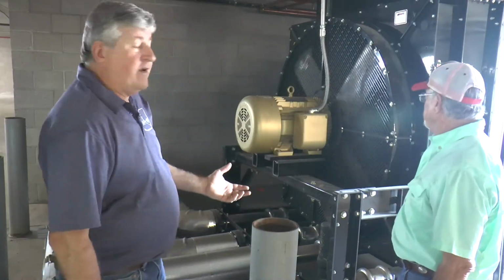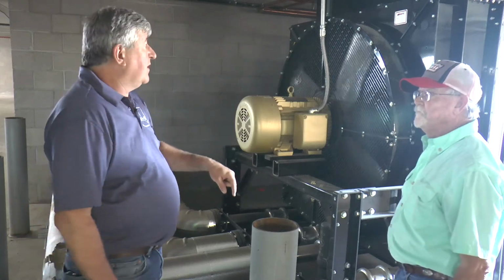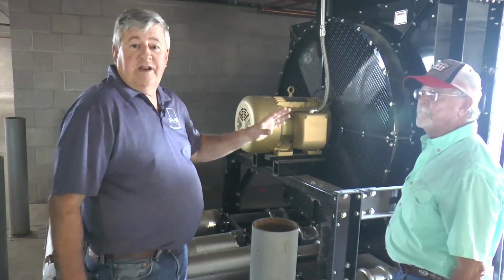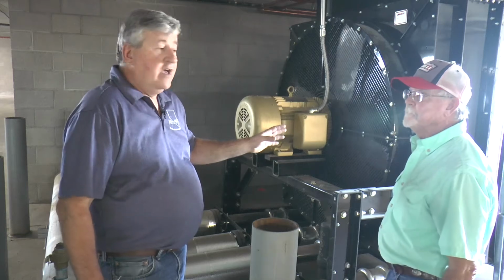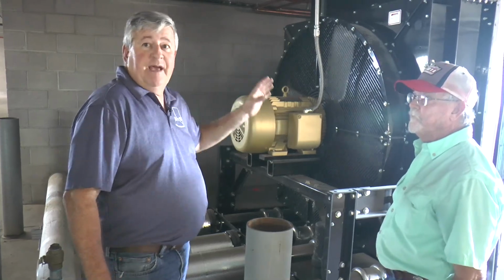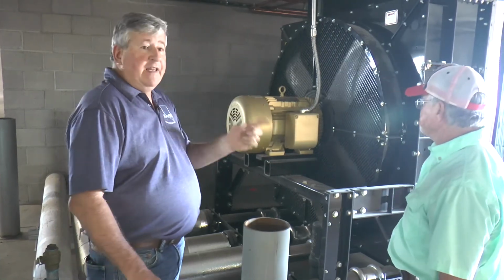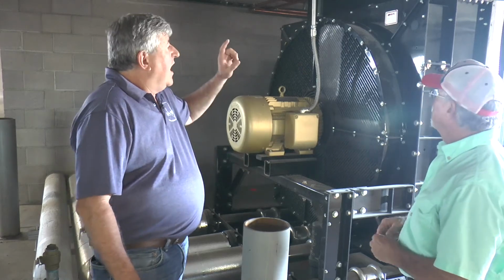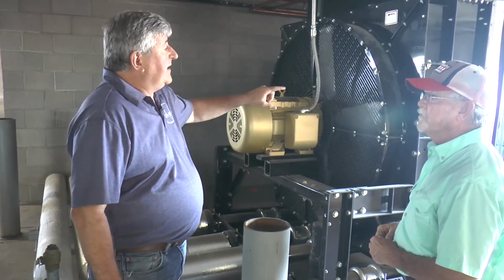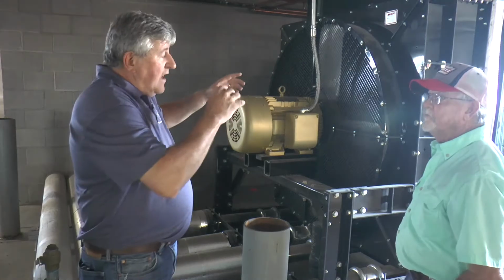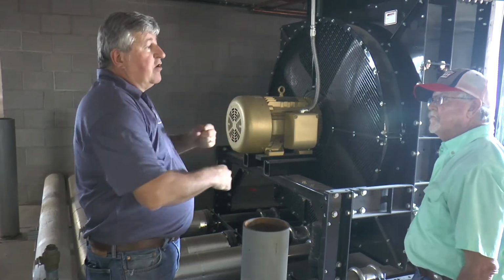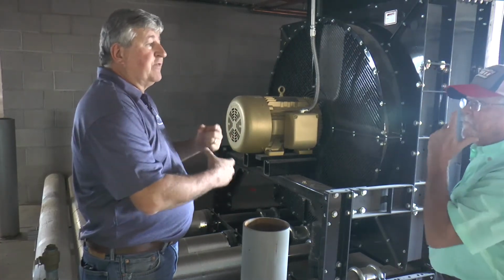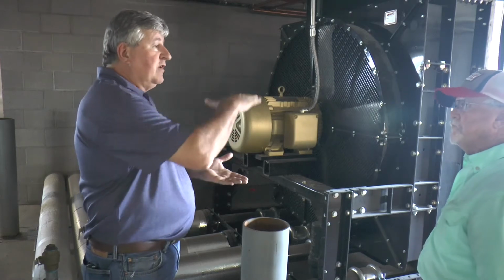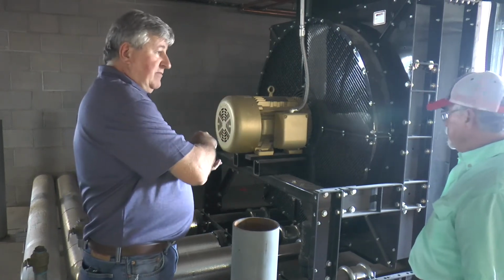This is the remote radiator for the generator that's located on the first floor. This radiator will start at any time the generator starts. It runs anytime that generator is running. In the event that there's a failure and the fan shuts down, circulating pumps are still going, you're probably going to have a little more reserved coolant in there until that coolant level gets to a point to shut the engine down.